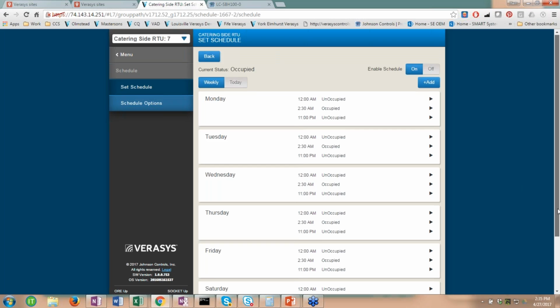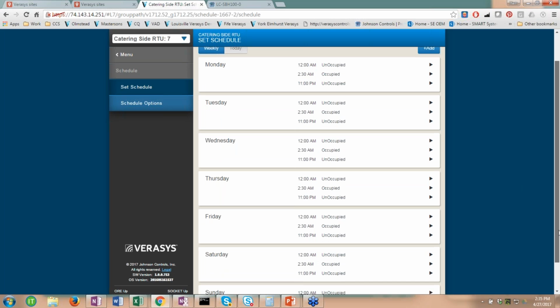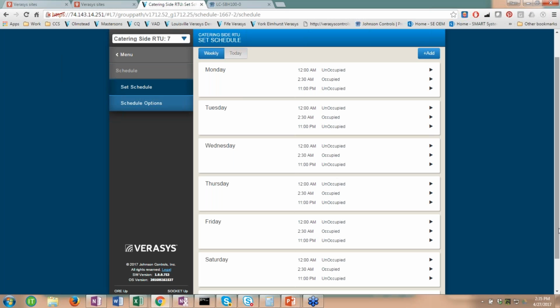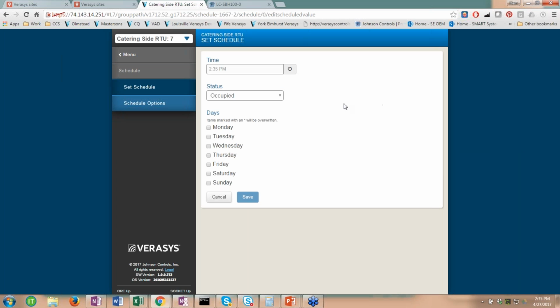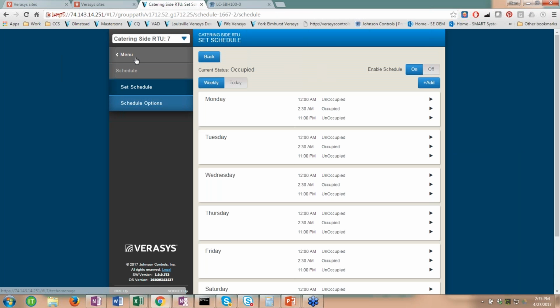One of the nice features is that every controller holds its own schedule. So if you ever lose connection to the Smart Building Hub, it really doesn't matter. The Smart Building Hub is nothing more than an eye into the system. I'm allowed to go through the SBH right now, Smart Building Hub, and I'm able to do what you're seeing on the screen right now. But again, all the smarts are pushed down to the controller level. So these schedules that I'm showing you right now, and you could go in and add new things if you need to, are being saved down to the controller level.